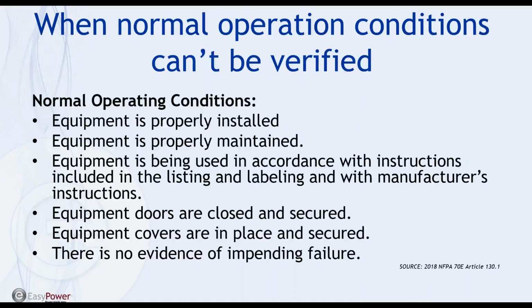Another situation is when normal operating conditions cannot be verified. Looking at NFPA 70E, specifically Article 130.1, you'll see exceptions around how you approach arc flash safety based on normal operating conditions. You have to make sure equipment is properly installed and maintained, used in accordance with manufacturer instructions and listings, equipment doors are secured and closed, covers are in place and secured, and there's no evidence of impending failure.